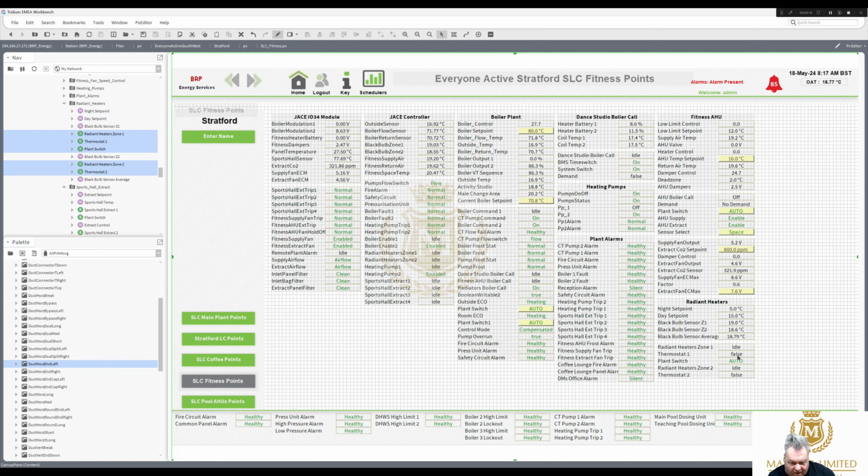False thermostat. Could be a high thermostat, but saying that, none of the heaters are working, so we probably won't be using thermostat 1 and thermostat 2 in the graphics. We would just have the zone 1, zone 2, and we've got the temperatures for zone 1, zone 2. We've got the average. We've got a day set point and a night set point there.